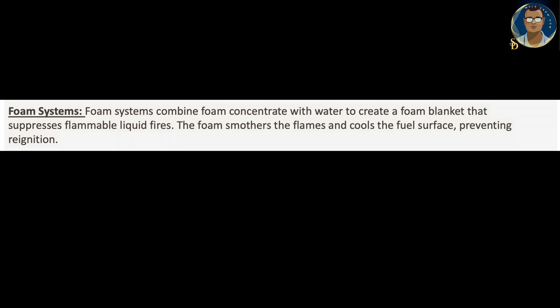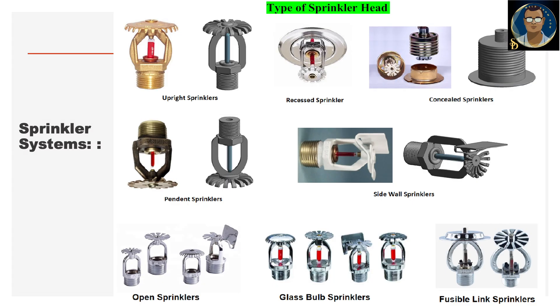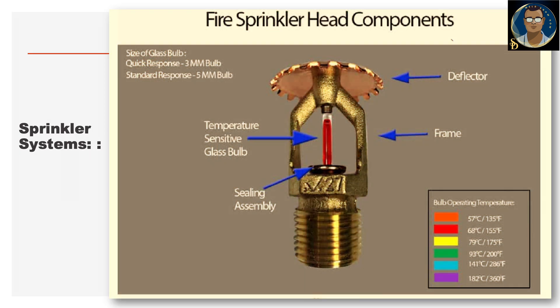Here are some sprinkler photos for your information and knowledge. Fire sprinkler head components — a sprinkler basically has a temperature-sensitive glass bulb and a frame to hold everything, plus a deflector that deflects the water downwards when it sprinkles. Regarding glass bulb properties: quick response uses a 3 mm bulb and standard response uses a 5 mm bulb. The bulb operating temperature ranges from 57°C to 182°C, and the appropriate bulb should be selected based on the facility or building's safe temperature.